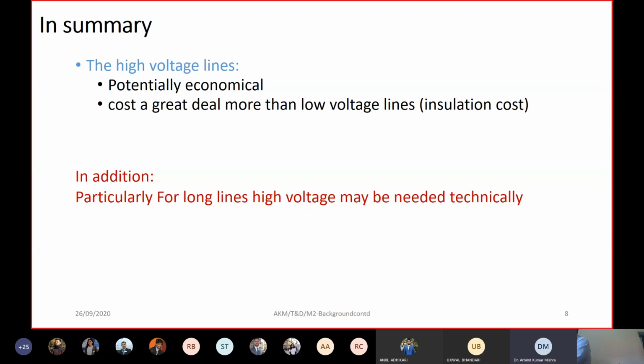Per unit power to be transmitted cost is lower for high voltage lines, but these high voltage lines have higher capacity. These are economical only if you have to transmit a very high amount of power. For a lower amount of power, the per megawatt transportation cost is higher, but still we use the lower voltage case.